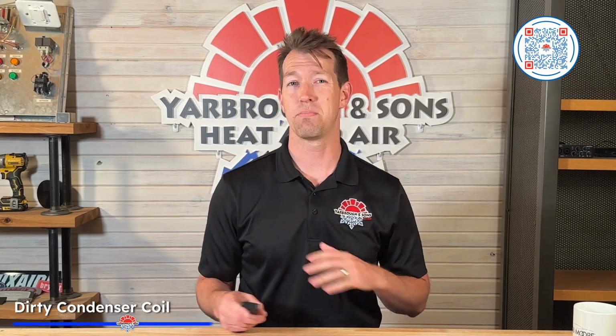If your outdoor unit has cottonwood packing the fins, which are those little bitty metal slats, this spring and nobody's cleaned it, you are running a compromised system right now. A professional coil cleaning runs somewhere between $100 to $400, depending on the condition of the unit and the labor associated with that. So here's something you can do yourself.